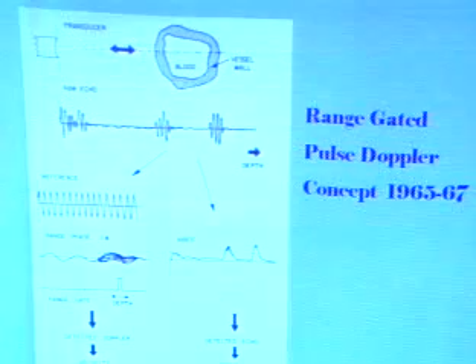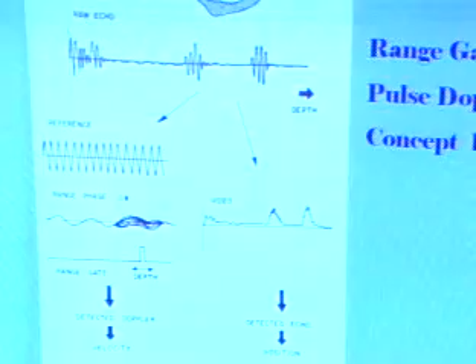It was a phase coherent pulse Doppler in which we had a reference frequency, and we could transmit a sample of that into the tissue and then compare the relative phase, which gives a phase modulated signal at the particular depth of the vessel, which we could range gate, and we could know now where is it coming from and how fast is it moving. We could also tell which direction it's going. This also gives us the possibility of getting position information by getting echoes off of the structures that are there.